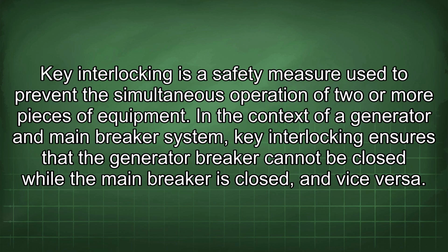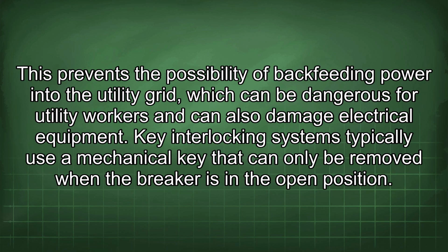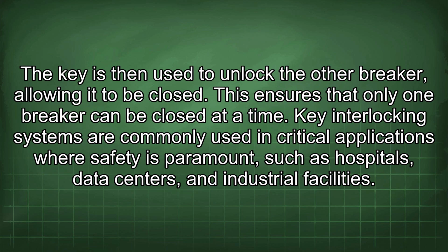Key interlocking is a safety measure used to prevent the simultaneous operation of two or more pieces of equipment. In the context of a generator and main breaker system, key interlocking ensures that the generator breaker cannot be closed while the main breaker is closed, and vice versa. This prevents the possibility of backfeeding power into the utility grid, which can be dangerous for utility workers and can also damage electrical equipment. Key interlocking systems typically use a mechanical key that can only be removed when the breaker is in the open position. The key is then used to unlock the other breaker, allowing it to be closed. This ensures that only one breaker can be closed at a time.